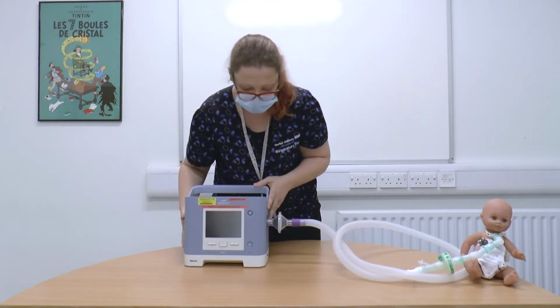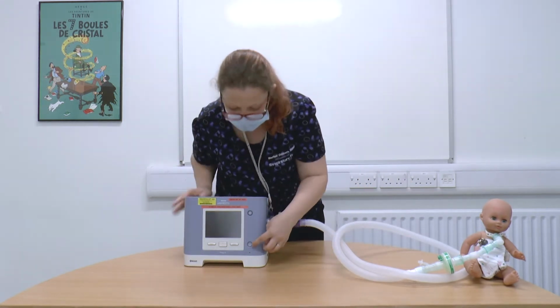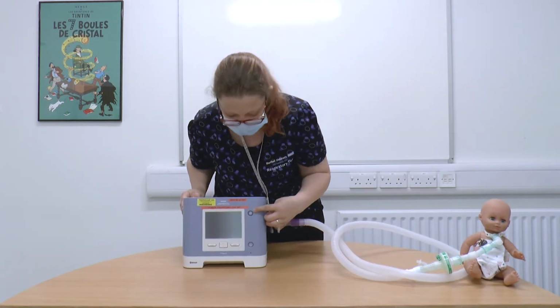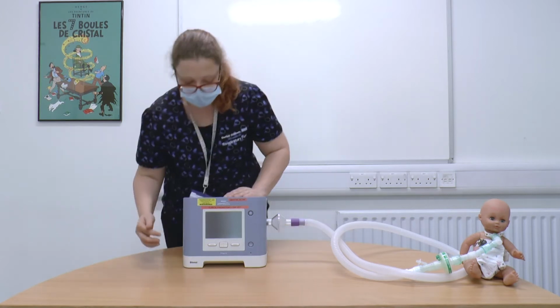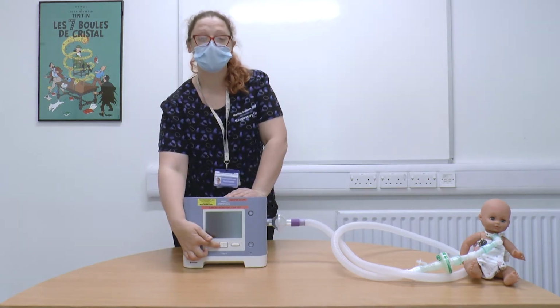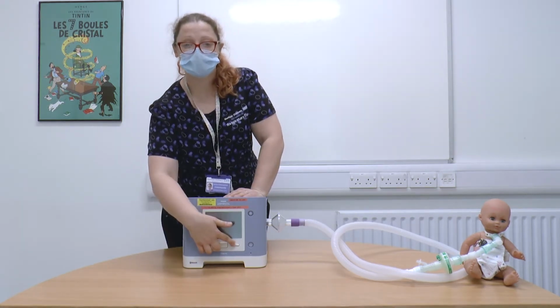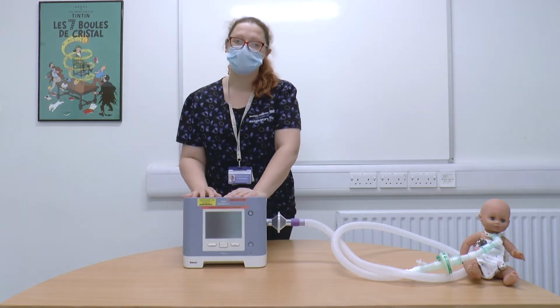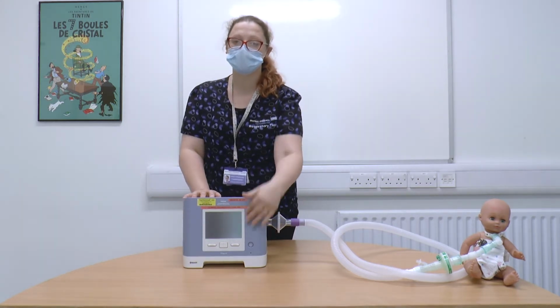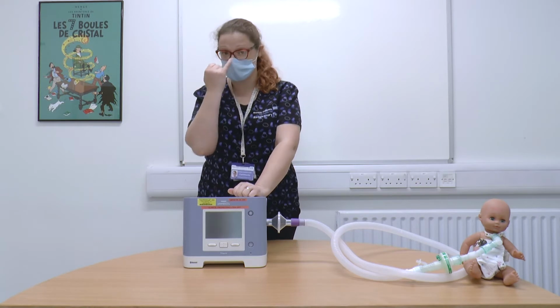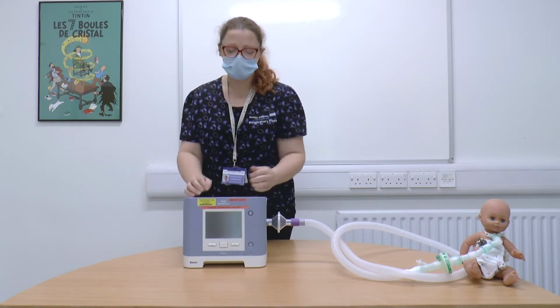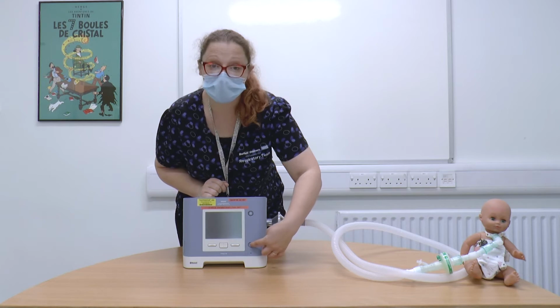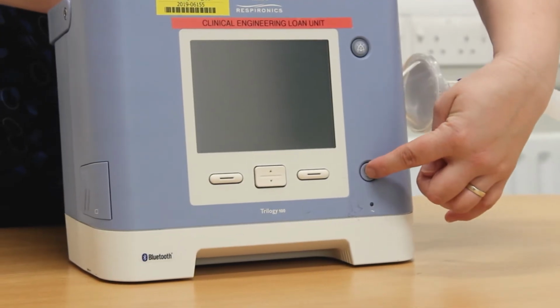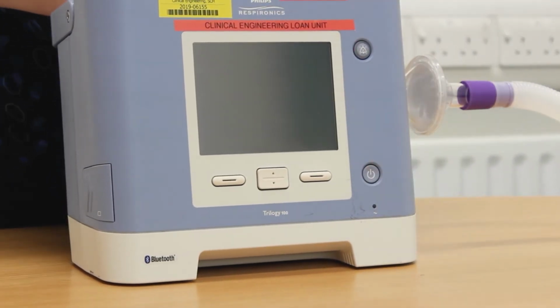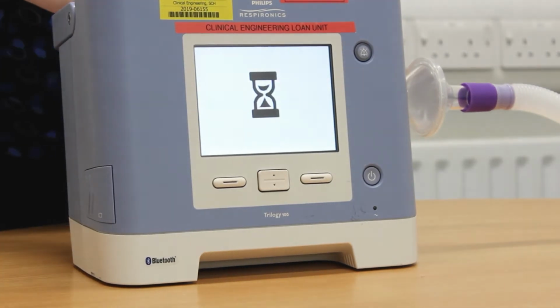On the front of the machine, you will notice there is a power button and a silence button. Then at the base we have an up-down arrow and 2 selection buttons. This is not a touchscreen ventilator. Everything is required to be done by the buttons. You turn the ventilator on by pressing the power button. It will automatically start to blow once it's gone through its self-checks.